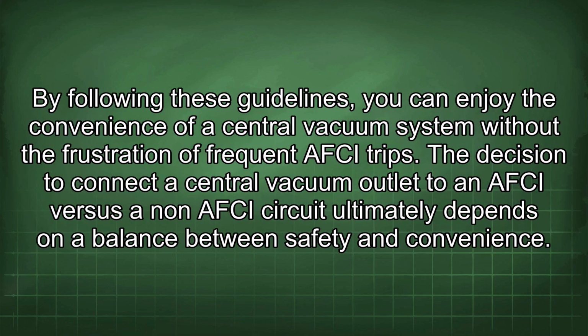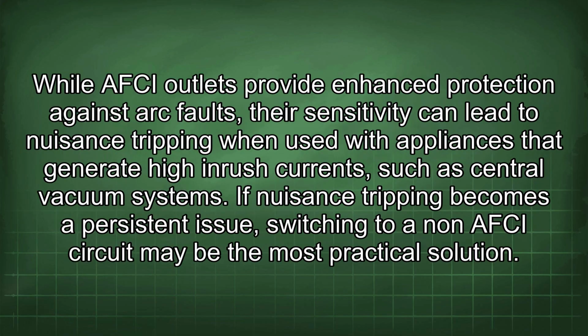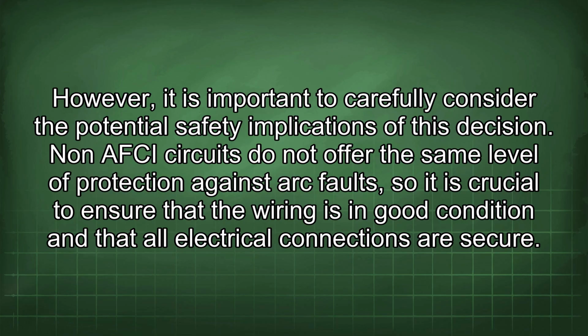By following these guidelines, you can enjoy the convenience of a central vacuum system without the frustration of frequent AFCI trips. The decision to connect a central vacuum outlet to an AFCI versus a non-AFCI circuit ultimately depends on a balance between safety and convenience. While AFCI outlets provide enhanced protection against arc faults, their sensitivity can lead to nuisance tripping when used with appliances that generate high inrush currents, such as central vacuum systems. If nuisance tripping becomes a persistent issue, switching to a non-AFCI circuit may be the most practical solution. However, it is important to carefully consider the potential safety implications of this decision.